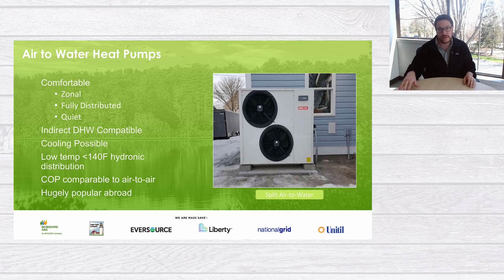Another nice thing about it is, say, the smallest ductless mini split is like 6,000 BTUs. Say it is easy for a hydronic system designer to be putting in 2,000 BTUs worth of low temperature baseboard or a 2,000 BTU radiator. So there's a lot more potential flexibility with design. Another nice thing about air-to-water heat pumps is they can also do domestic hot water. So you're not thinking about a hybrid hot water heater that is potentially stealing heat from the basement when having more heat in the basement may be favorable some times of the year.